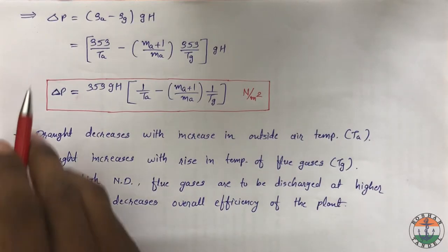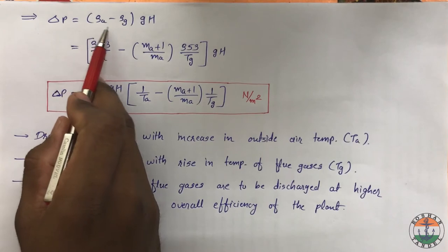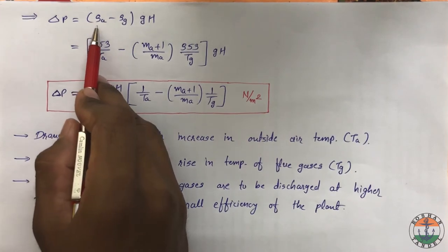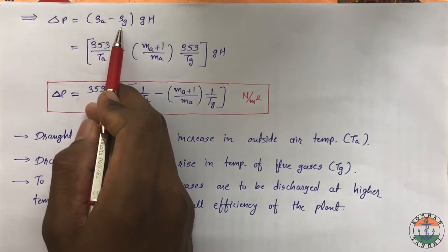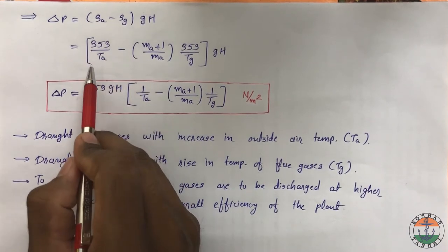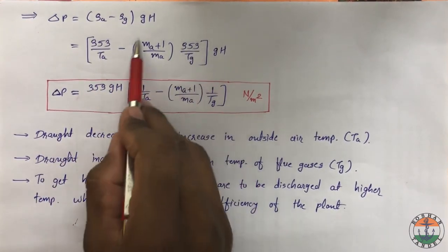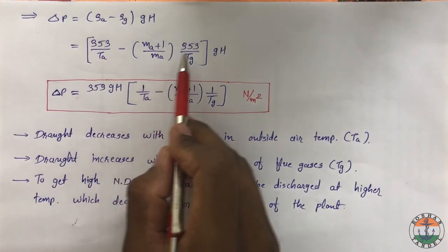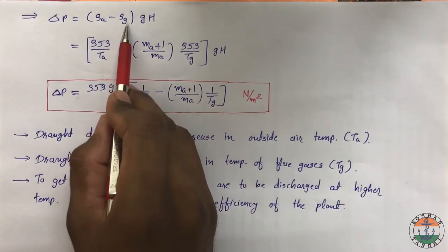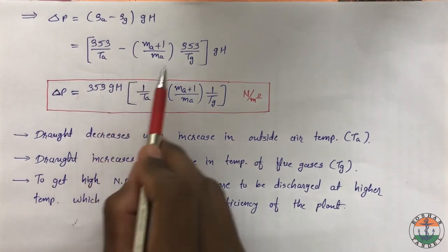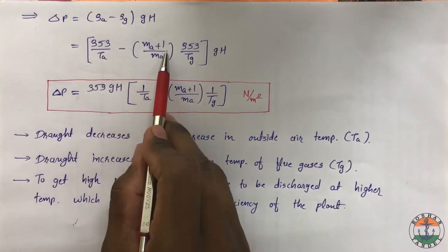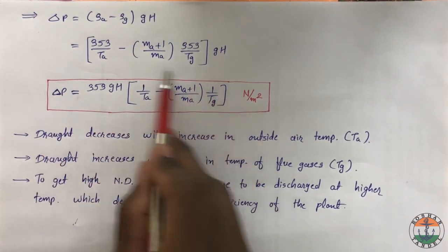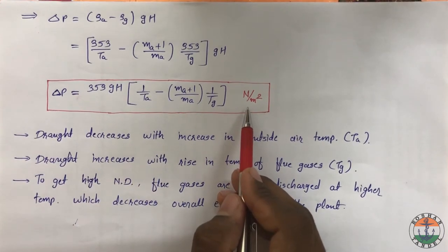Initially we have delta P = (rho_A − rho_G) × G·H. Substituting rho_A = 353/TA and rho_G = (Ma+1)/Ma × 353/Tg, and taking 353 common from both terms, we get the final form of delta P in Newton per meter square as: delta P = 353·G·H × [1/TA − (Ma+1)/Ma × 1/Tg].